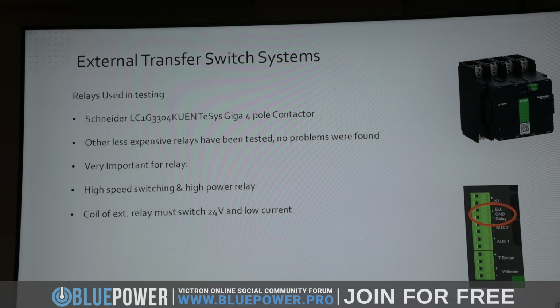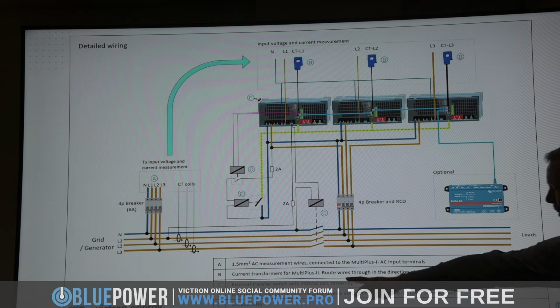External transfer switch - originally when we started with this, we said you could only use that one, the 4-pole, bigger, very expensive, 35,000 Rand contactor. But after a lot more testing, we can now confidently say you can use any high-speed, high-power contactor with that specification.